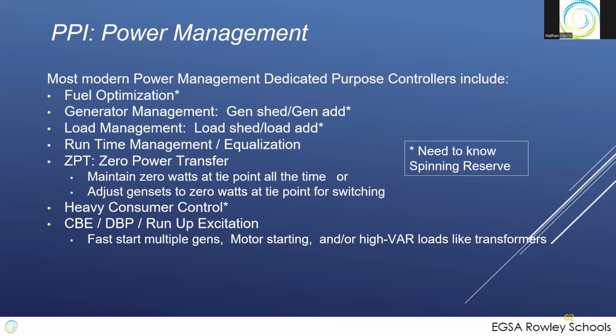The other definition of ZPT, and this is one utilities don't like as much, but we see it a lot in the northeast part of the US, is that you run your generator plant. You have a local power plant with a local load and a utility tie, and you run your local generation to equal your load being consumed on your system. So there's zero power at the utility tie point.